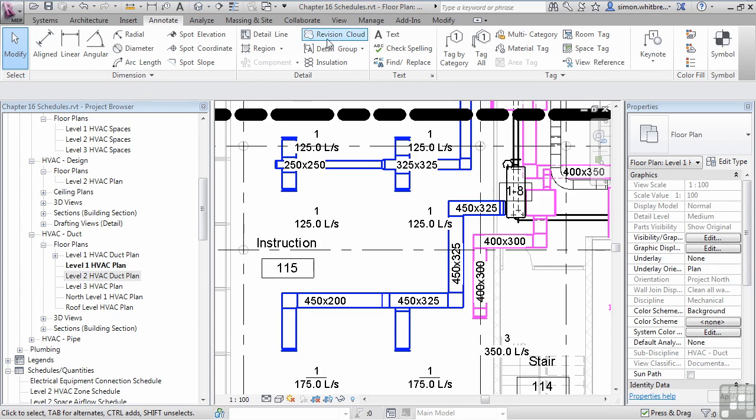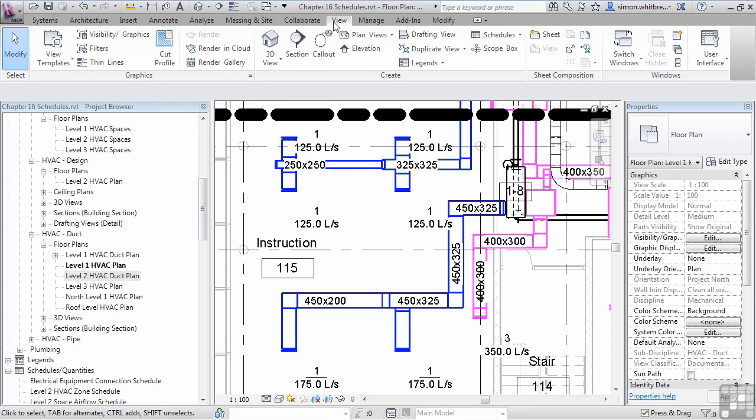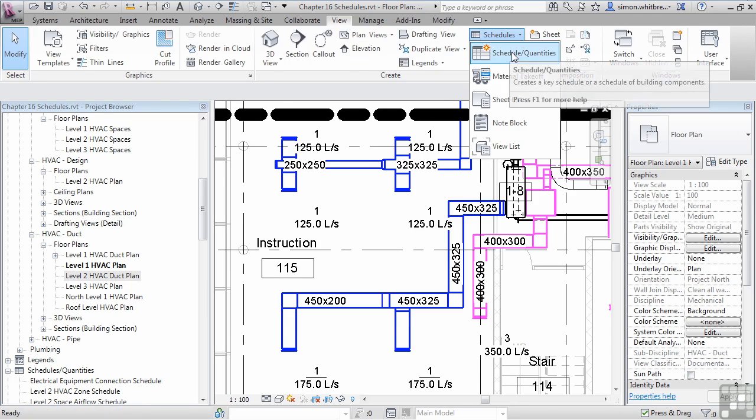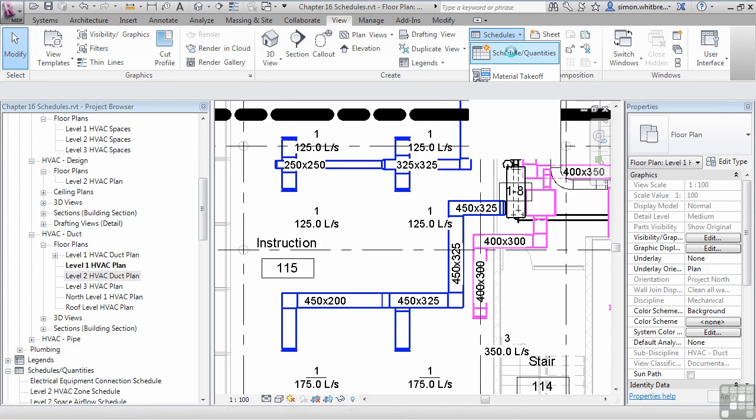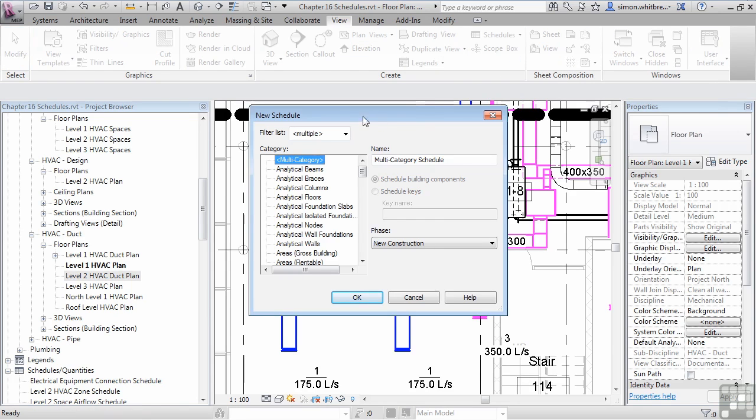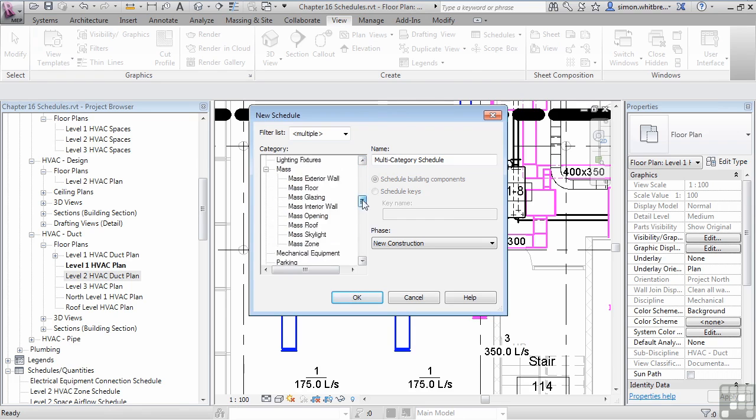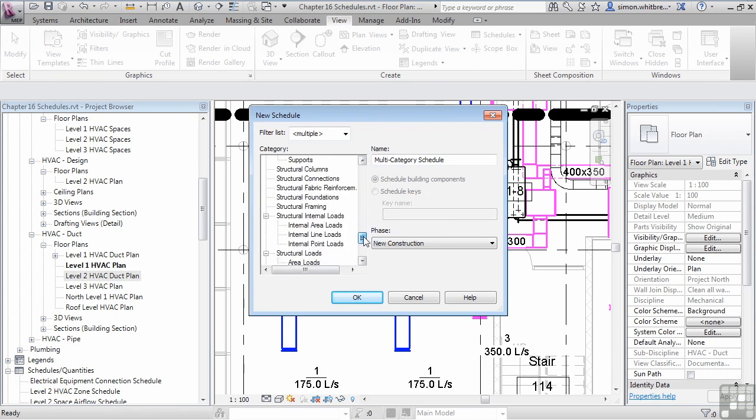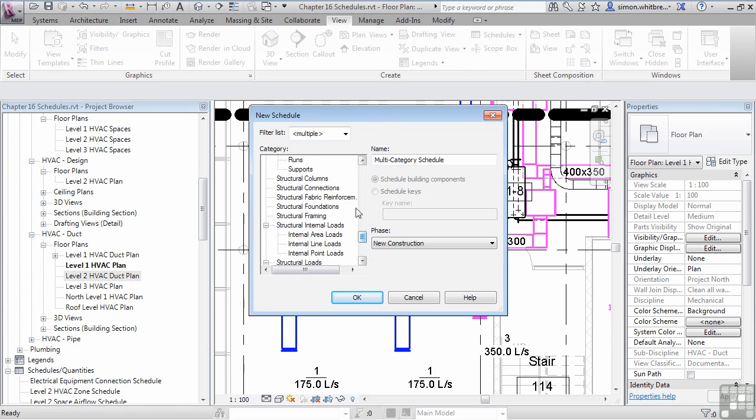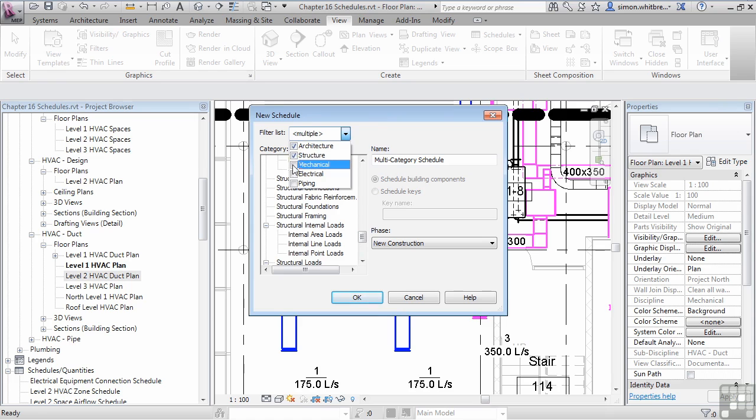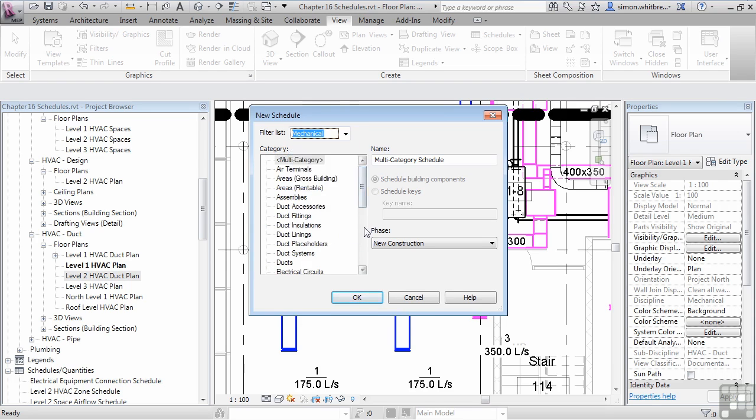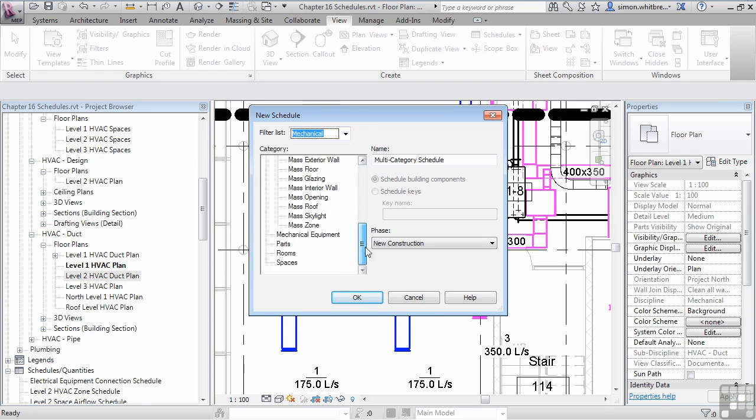From the View tab, click on Schedules, click on Schedule Quantities and scroll down in the category list until you find Spaces. As you can see here, I can't find them. There is a filter on this list. We need to make sure that Mechanical is selected. Then we have Spaces. Click on OK.